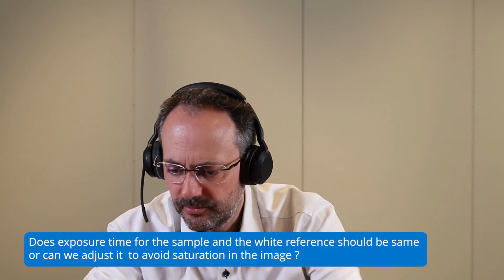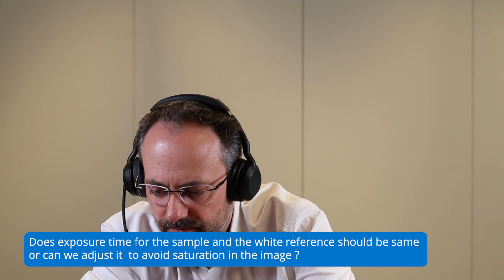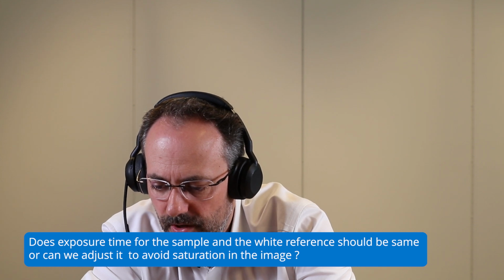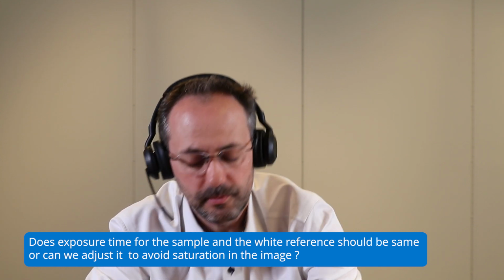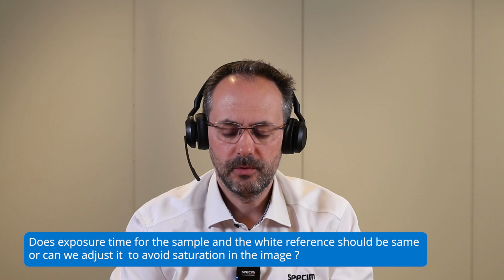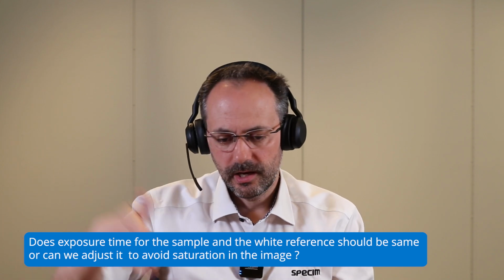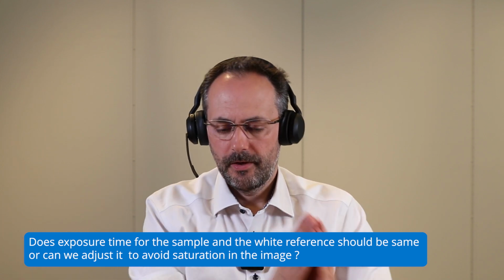Should the exposure time for the sample and the white reference be the same, or can we adjust it to avoid saturation in the image? It is exactly what I was explaining with the dual integration time approach. Here, this is exactly the same. Typically, you acquire the white with a shorter integration time than the one you want to use to acquire your data, or you can play with that.